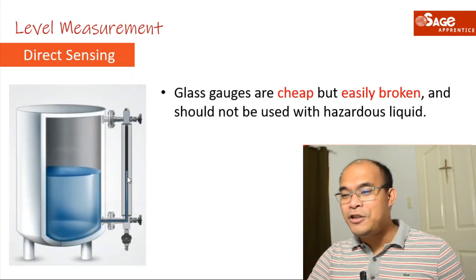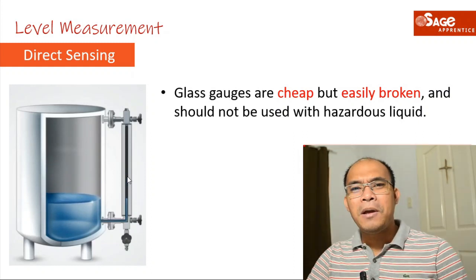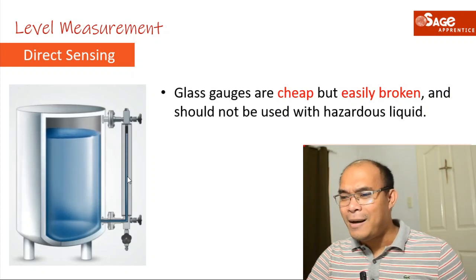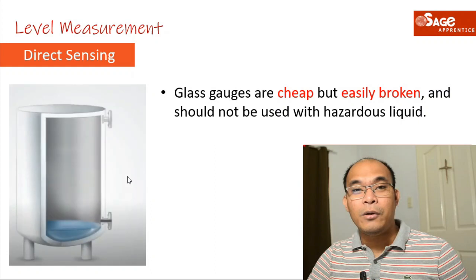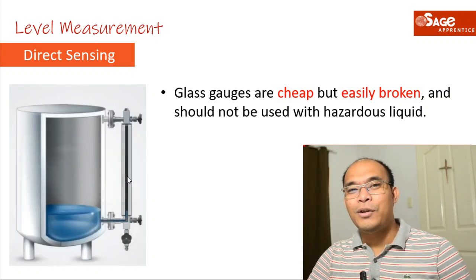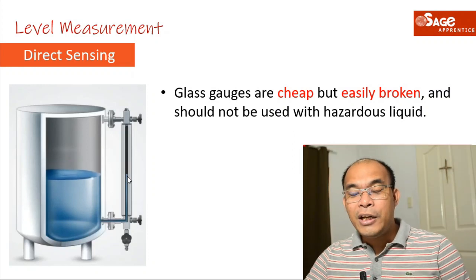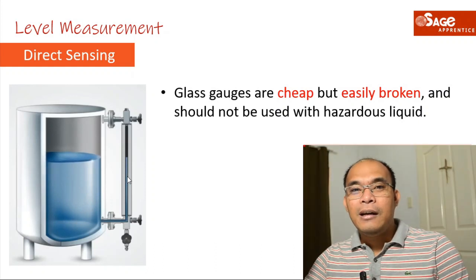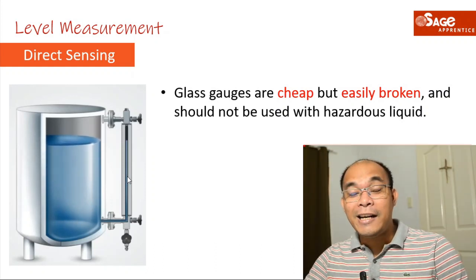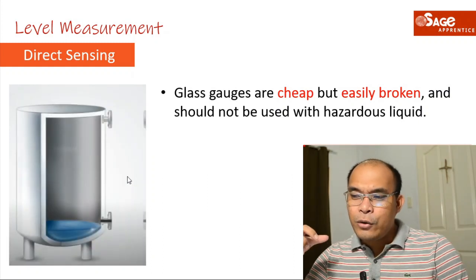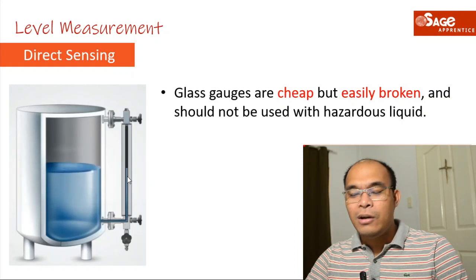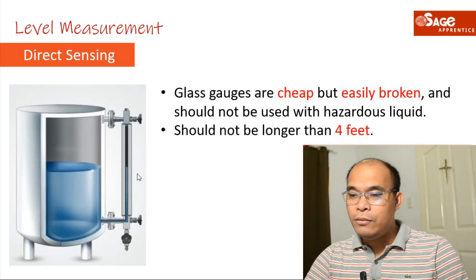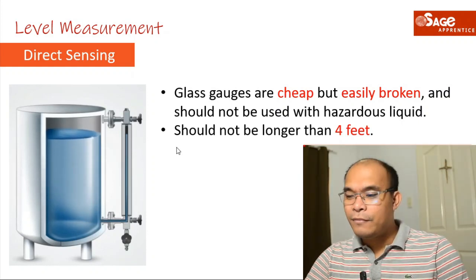The common characteristics of a sight glass: glass gauges are cheap but easily broken since glass is a fragile material. They should not be used with hazardous liquids — if the glass breaks and the tank contains hazardous material, it puts engineers at very high risk. The sight glass should not be longer than four feet.